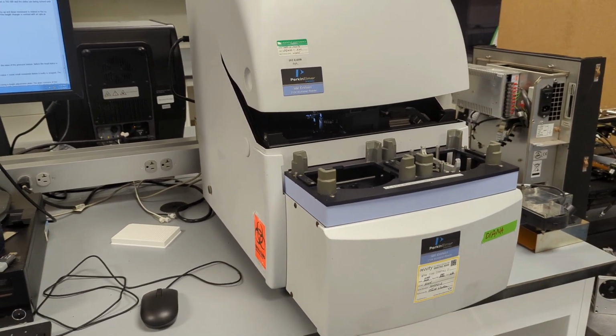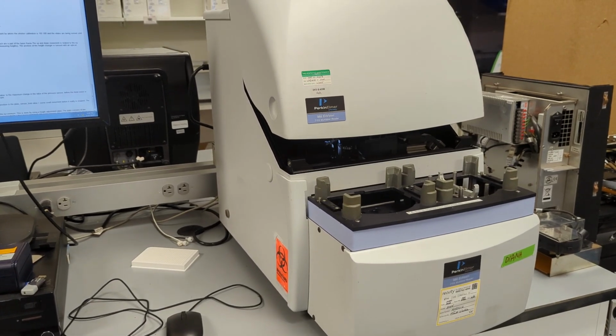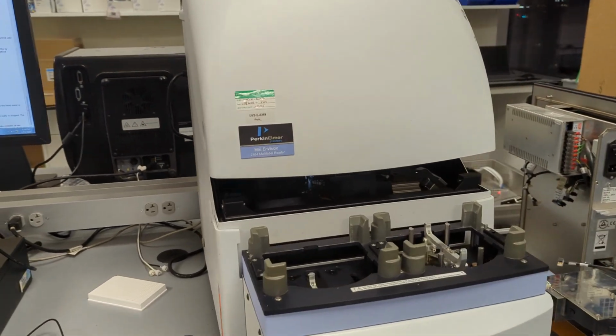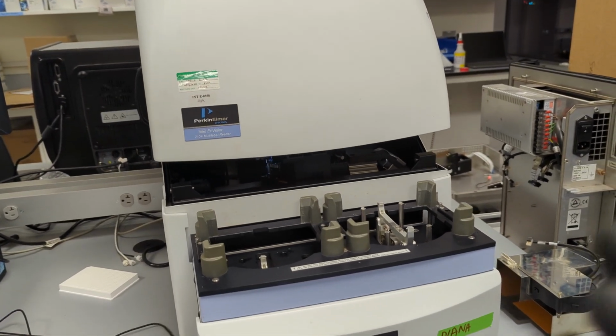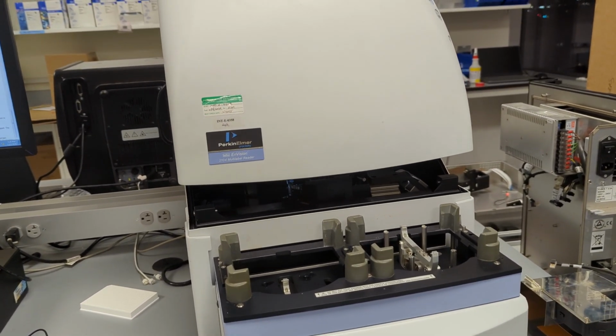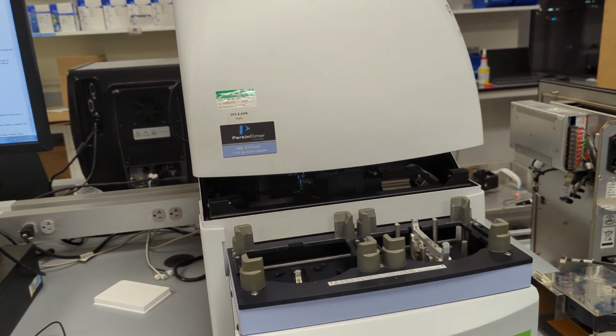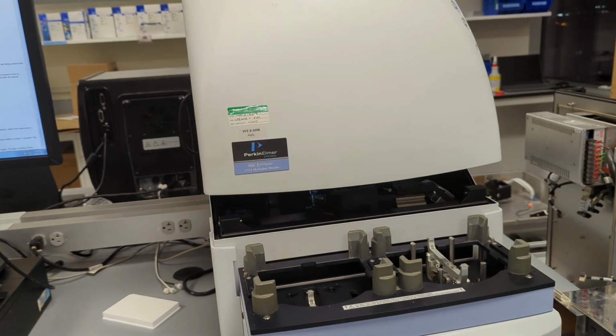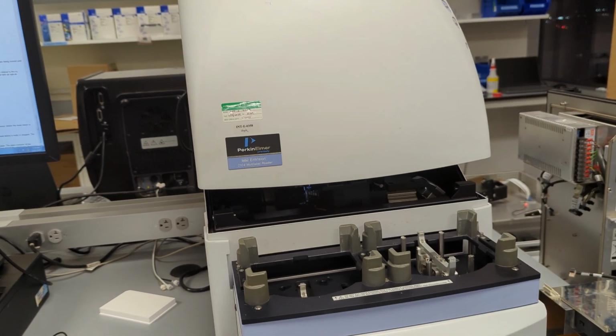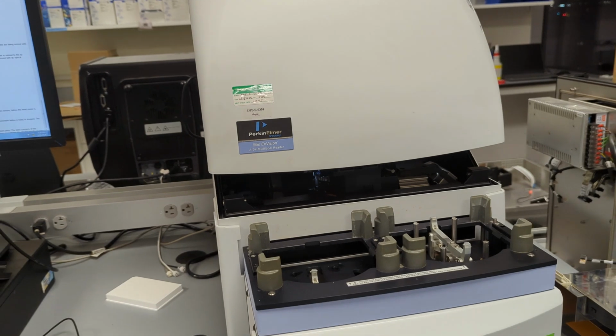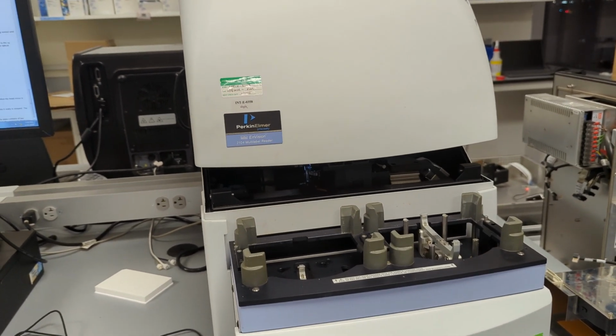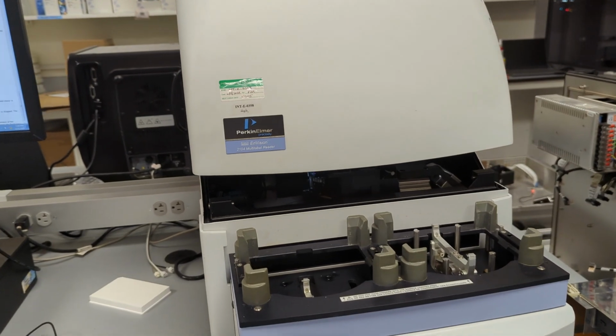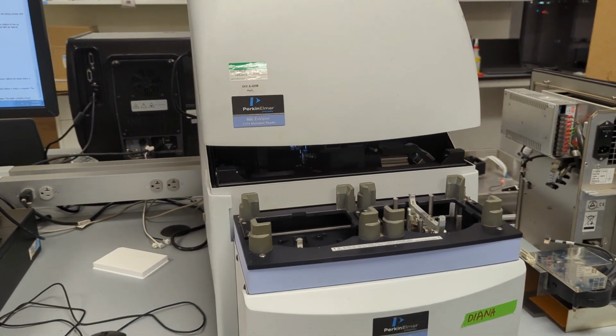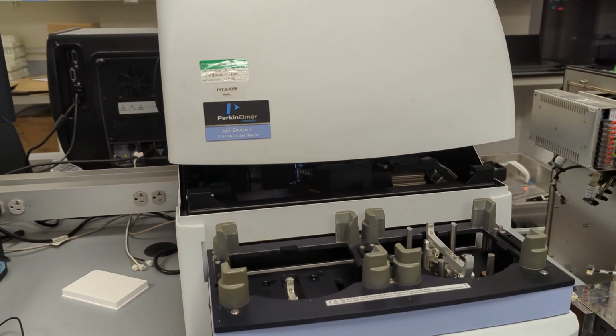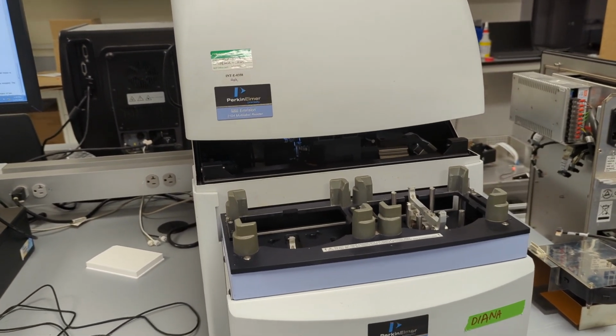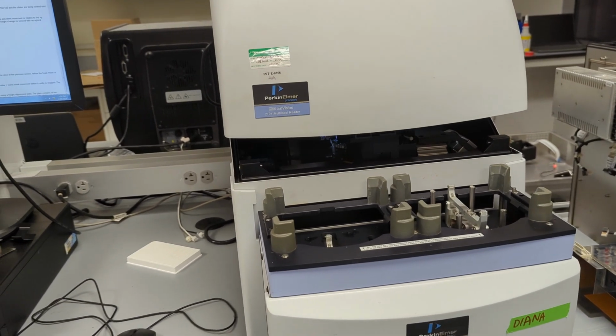You can't do that with the Envision because PerkinElmer keeps the tools proprietary. There are certain tools that you need to ensure that the measuring head is coming down to the correct height. All of these things need to be checked with standards that PerkinElmer does not sell to their customers. And so what does that mean? If you want one of these, you really can't avoid a service contract. And if you work in the lab, I'm sure you know, service contracts are expensive. And so with the purchase of one of these, and a lot of instruments, the cost does not end with the instrument.